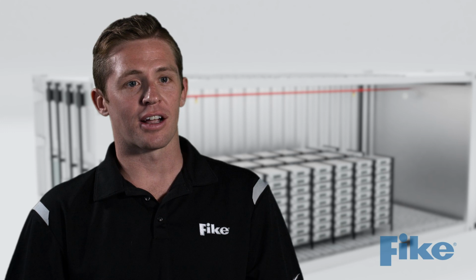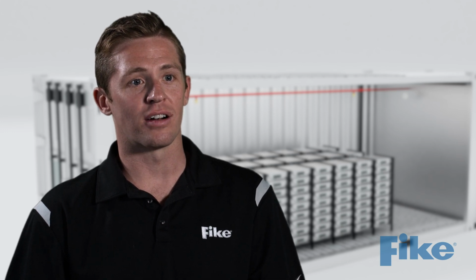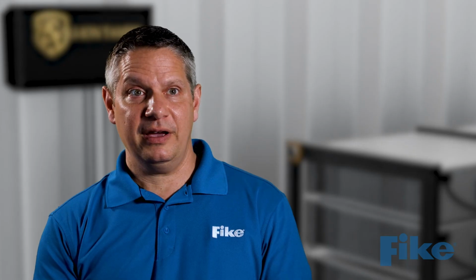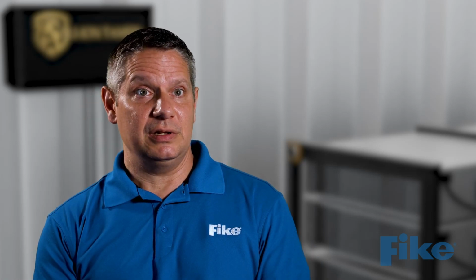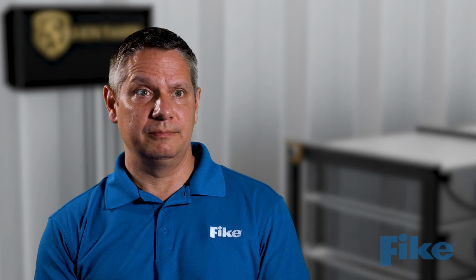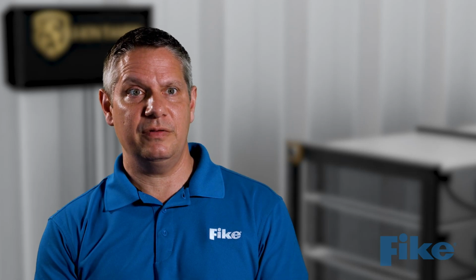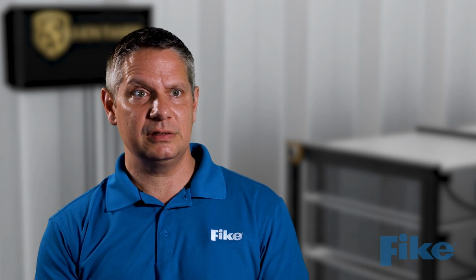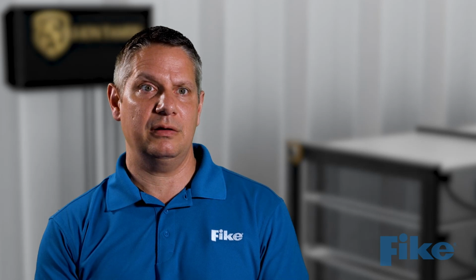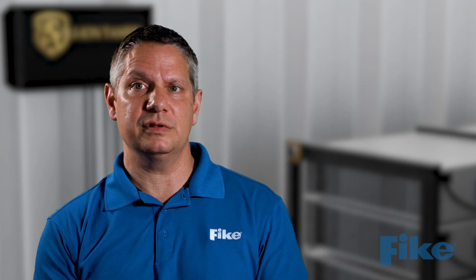The next layer of protection is equipping the enclosure with a fire detection system. One of the most impactful decisions you can make is the method of detection. Even if a fire suppression system is not installed, detection is still essential. It can help activate HVAC vents to remove the explosive off-gases, shut down the power, sound alarms, and notify emergency responders of the situation.